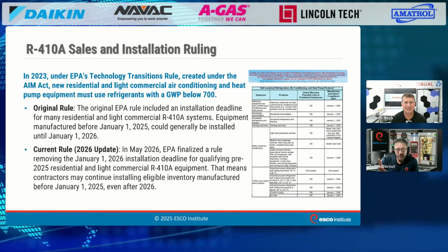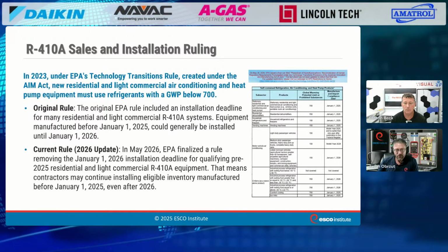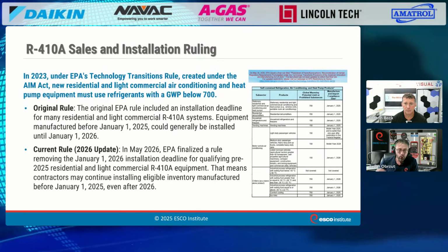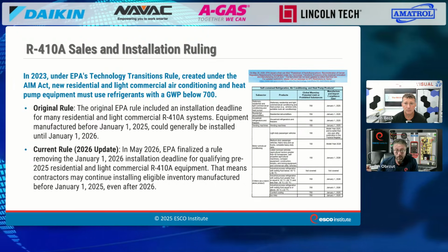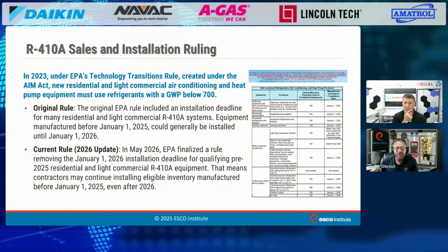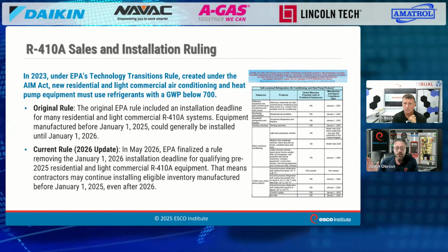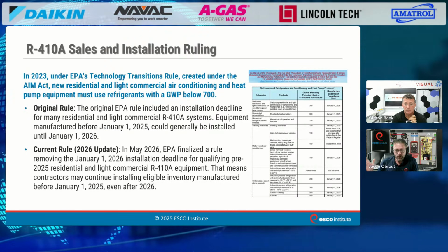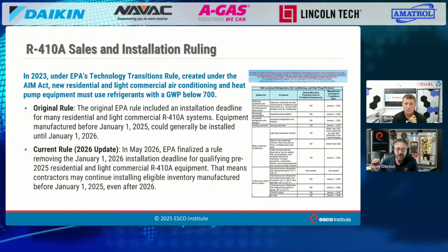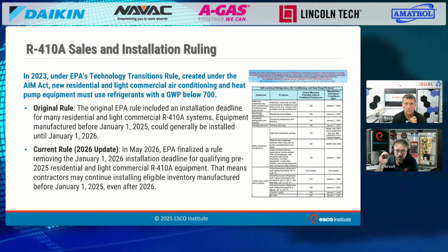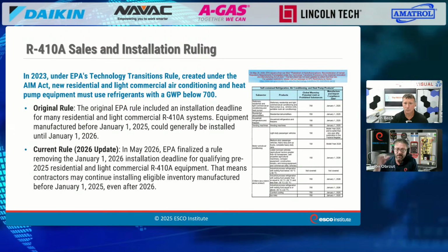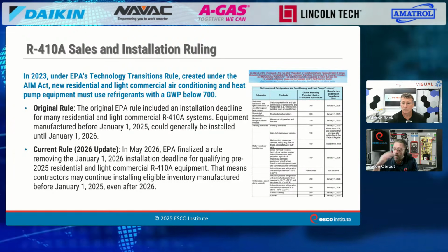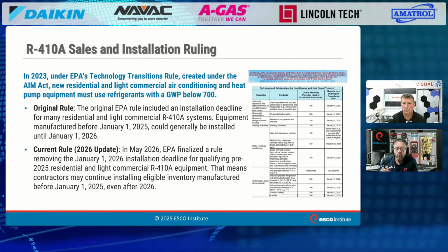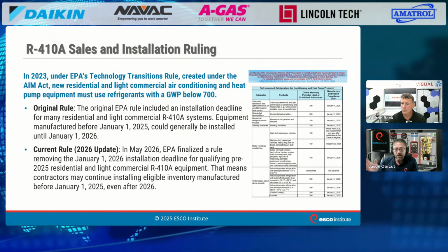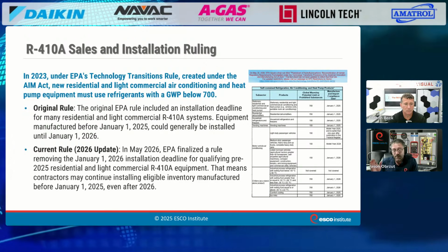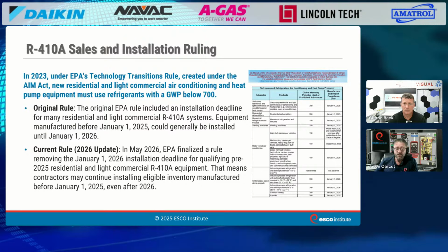So as you mentioned, we're in a phase down of refrigerants, right? These HFC refrigerants, higher GWP. What this rule is doing is phasing out the equipment that runs on those refrigerants. So what the EPA has done is separate the industry into about 39 different subsectors. And then for each of those subsectors, it assigned a GWP limit saying, all right, for this sector, it is 700 and the date of manufacturing is this, which means we can't make anything above that GWP limit after this date. So it's basically a phase out for all of the equipment that runs on these older, higher GWP refrigerants, again, based on the subsectors of the industry. And I believe it was 39 of them that it laid out.